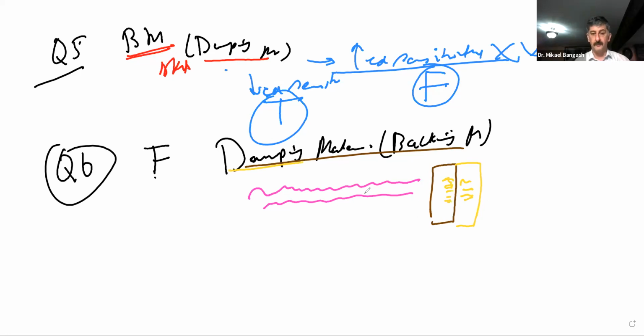And that means it goes from a continuous wave to just firing off in pulses. On the other side, you can also say that we have an increased bandwidth. And as a result of increased bandwidth, what we will have is shorter pulse durations. So as we said, the pulse duration is determined by the transducer. Clear? It's all dependent upon how much backing material they put into it.